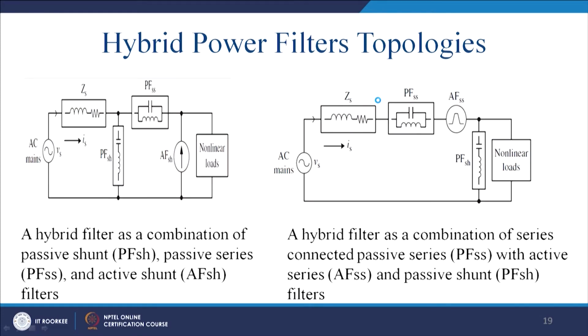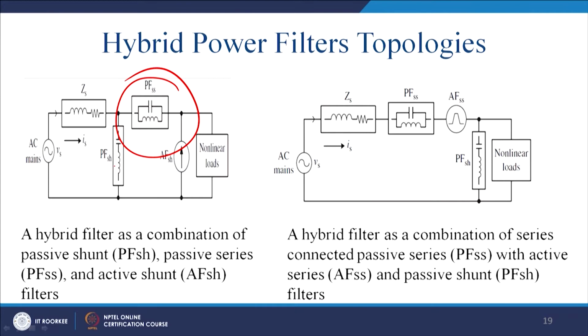And now we can have a T network. T network gives good amount of attenuation, as you know. This is a pi network. Here passive, the first passive, will sink more, taking out the main bulk of the harmonic contamination. Then this will block the fifth and seventh voltages mainly, and thereafter this will mitigate the remaining part of the harmonic based on the mitigation, because it may detune due to fluctuations of the voltages, and thus you may not get the desired THD, and ultimately this will have a final cleanup operation.